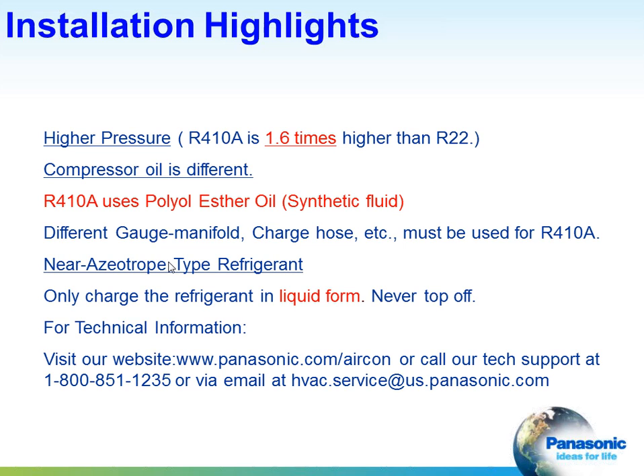But don't try to use piping from a conventional split AC system for two reasons. One, the sizing will probably not be correct. Two, there might be traps. We don't do traps with ductless split systems. Three, the oil is different. We're not using mineral oil here. We're using POE oil. You're going to be using different gauges. They must be R410A equipped, and even the use of R22 hoses can result in some contamination of the POE oil. Be careful there. Only charge the refrigerant in liquid form.